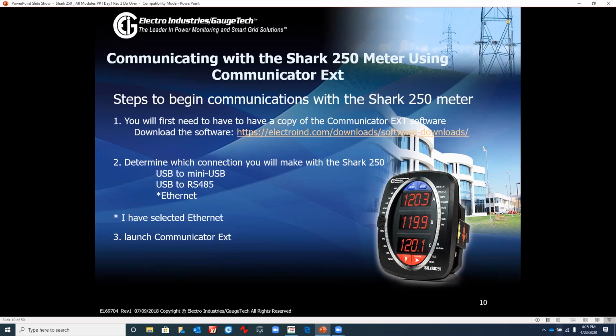And so in this particular case, we've gone through the USB, mini USB connection, the USB to RS485 and Ethernet. And I personally prefer to go to Ethernet because it's the simplest setup. When you choose this option, that's assuming that you have the Ethernet card purchased. You will need to set up your laptop computer to make sure it has the same address as the meter.